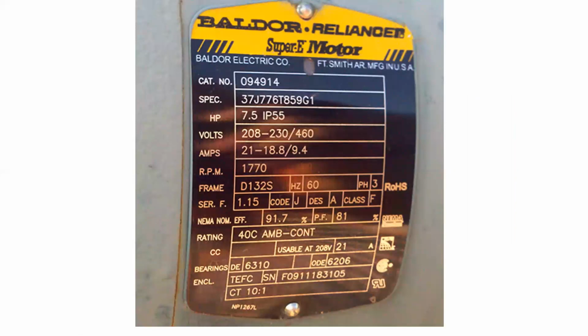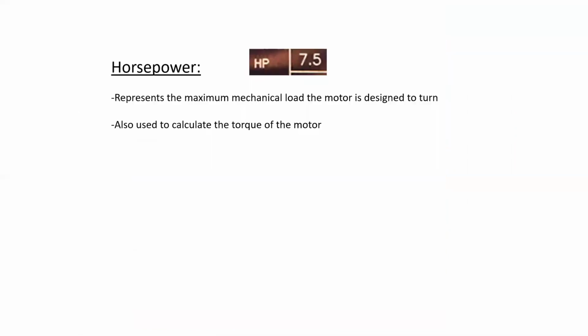Motor nameplates come in many different varieties, and we're going to take a little bit of time to really meticulously go through all of the different markings on this motor nameplate so that we have a general idea as to what each item is utilized for. So let's start off with the horsepower. The horsepower of this motor is 7.5. Now, the horsepower represents the maximum mechanical load the motor is designed to turn. It can also be used to calculate the torque of the motor, and we'll look at those calculations in a later presentation.